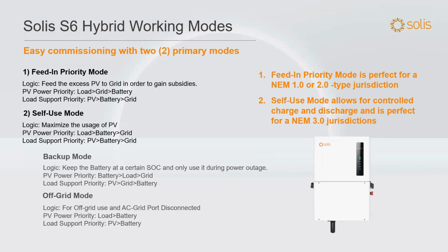The only reason you go into off-grid mode is that you're actually installing off-grid, so you don't have to switch to off-grid mode when the power goes out. You'll already be in off-grid mode. If you're setting this up with no grid reference, this is a grid-forming inverter, so you can set it off-grid and utilize these new high-voltage batteries for off-grid systems.